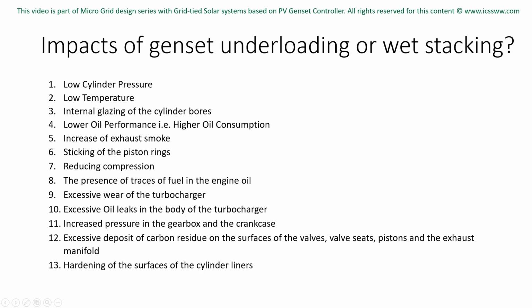Number 1. Low cylinder pressure. A diesel engine works by compressing hot air to an extreme extent so that when fuel is introduced into the cylinder, it ignites without the need for a spark plug. As a result, high cylinder pressure is integral to the proper working of the engine. When a generator is being run at low load, low cylinder pressure results in poor combustion, decreasing the efficiency of the engine. The poor combustion causes a cyclical issue. Soot and unburnt fuel residue clogs the already poorly sealed piston rings, making the low pressure problem even worse.